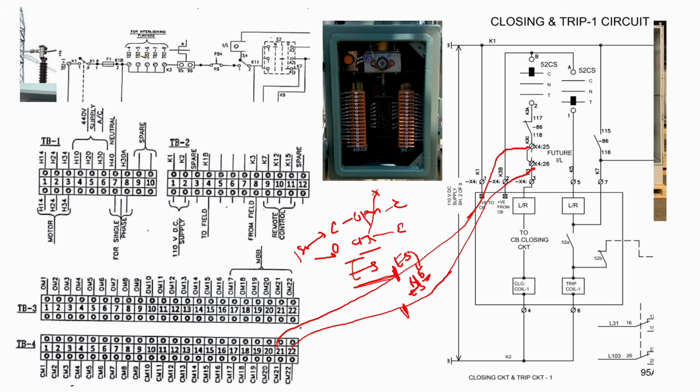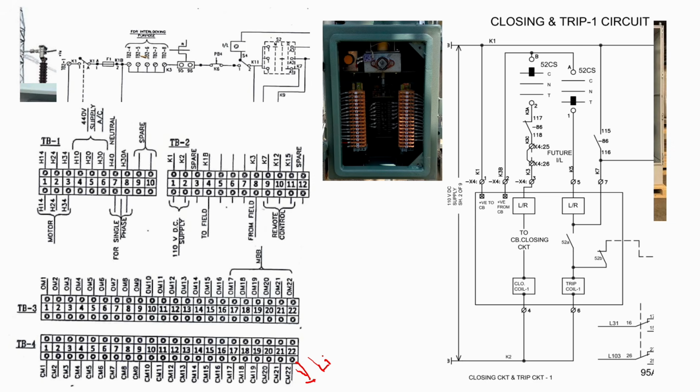Likewise, the same terminals you will find. Here this is an earthing switch box, so the same kind of terminals, TB3 and TB4, you will find here as well. This is my line isolator, this is my earthing switch, and this is my breaker connections, panel connections. So what I have to do: first my 21 will connect with this 21, and this 21 will reach TB number 425.